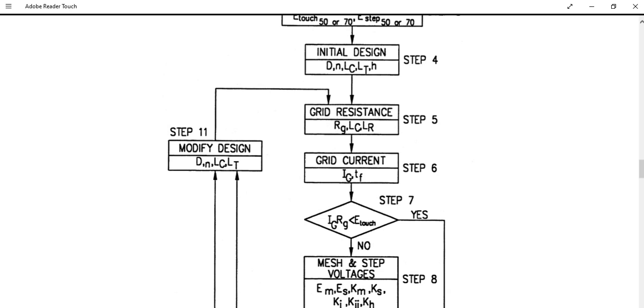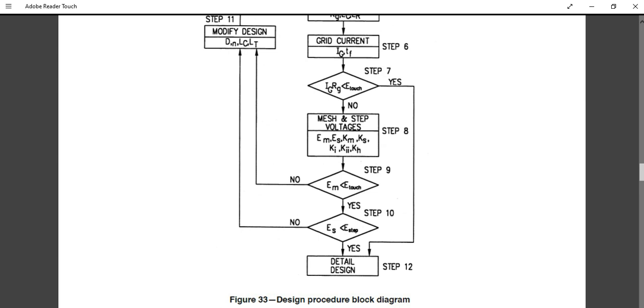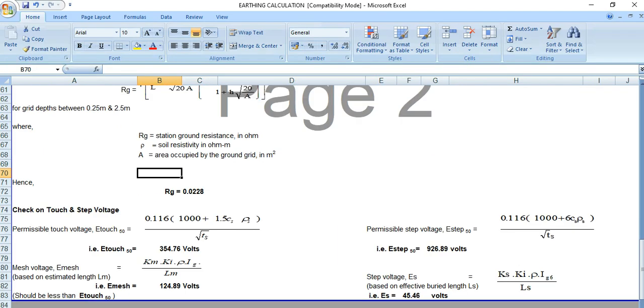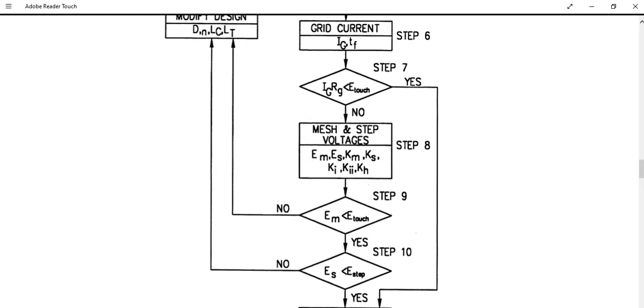Step 7 checks whether the ground potential rise (IG × Rg) is less than the tolerable touch potential. If this IGRG value is less than E-touch, the design is acceptable and you can proceed to the final design in Step 12. If Step 7 is not satisfied, you proceed to Step 8 to calculate mesh voltage EM and step voltage ES using formulas from IEEE 80.